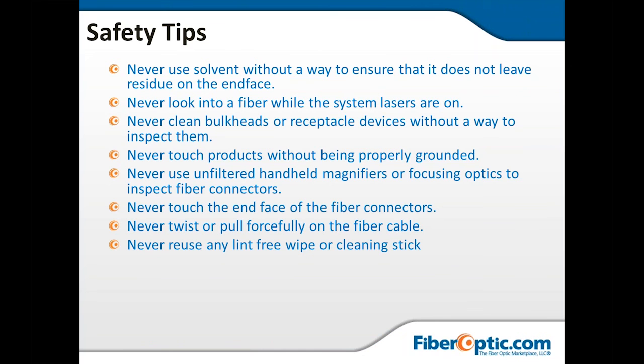Use one lint-free wipe once and then get rid of it, they're relatively cheap. Same with the cleaning sticks. Never touch the clean area of your lint-free wipe when you're cleaning, because you can get oil transfer from your hand onto the cleaning area and then onto your inspection connectors.